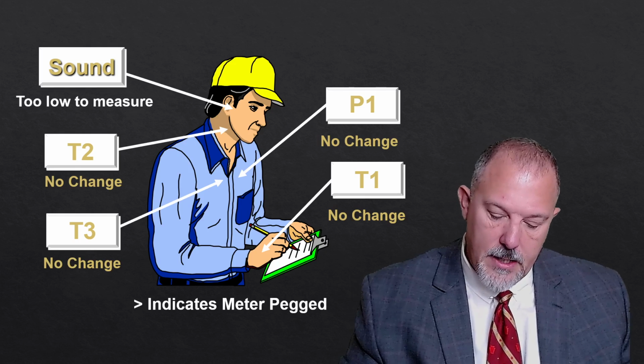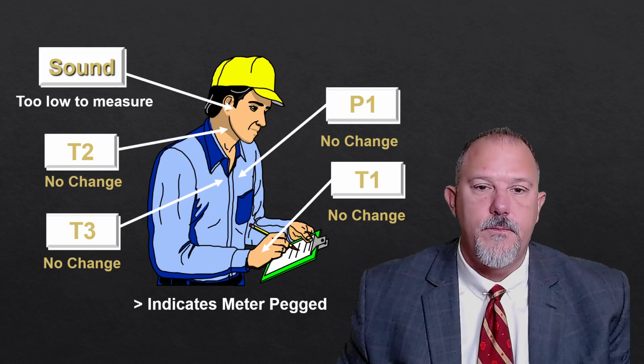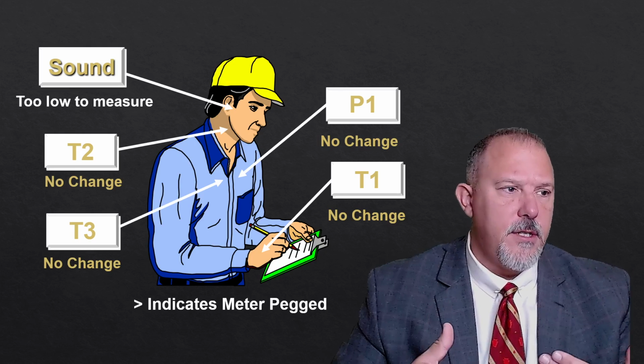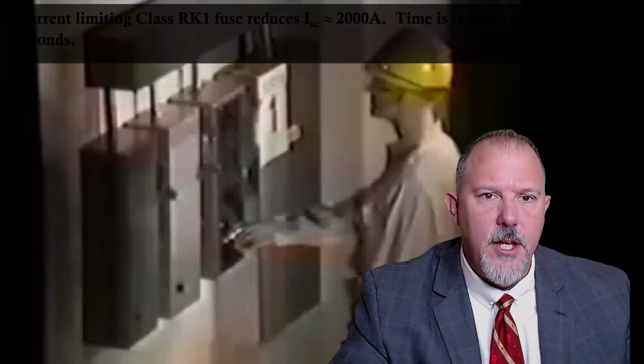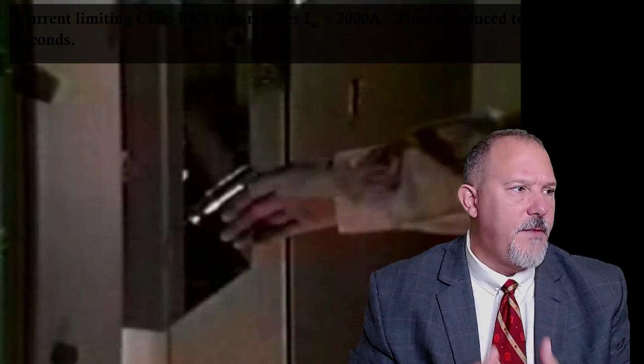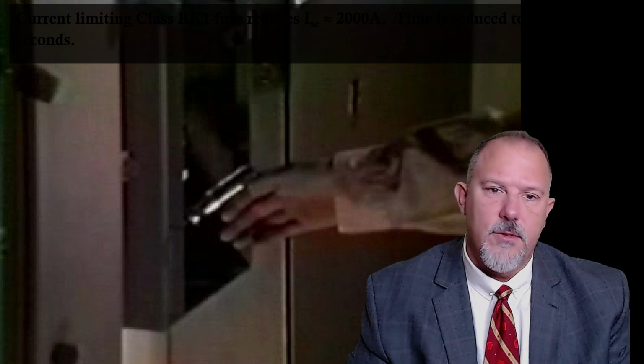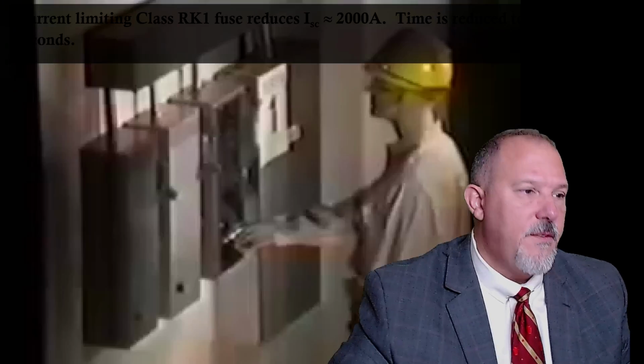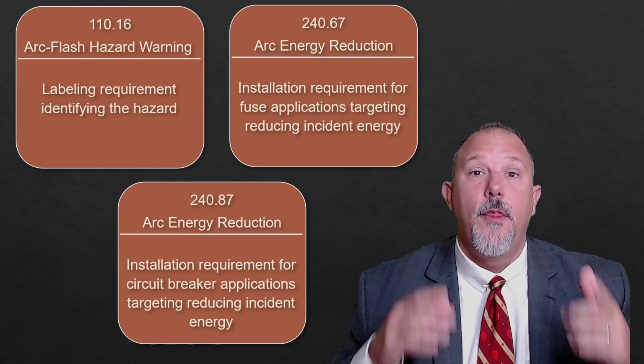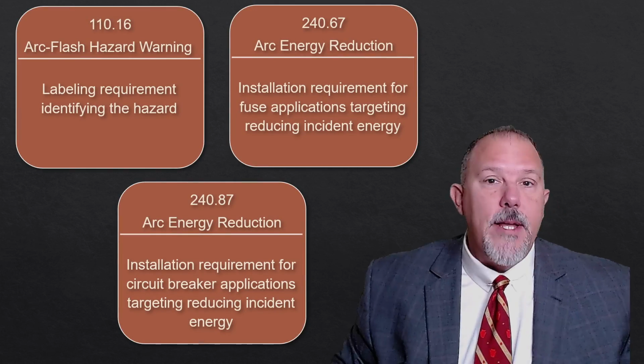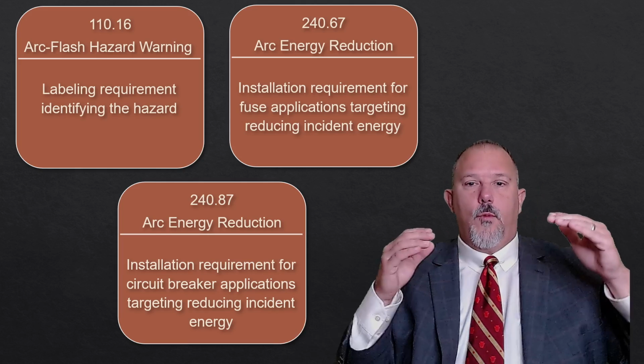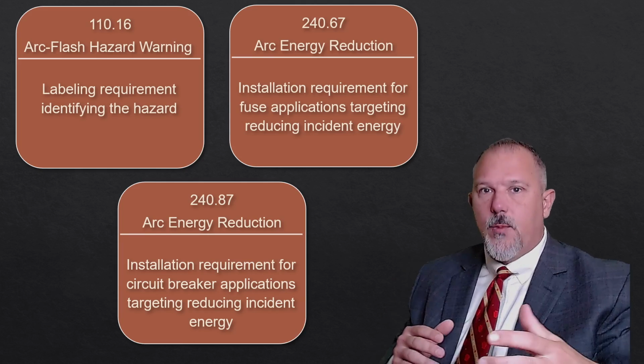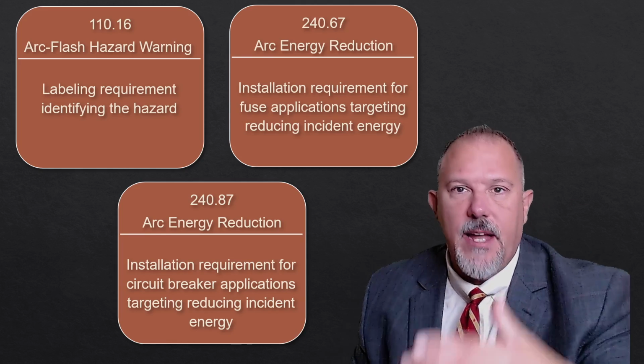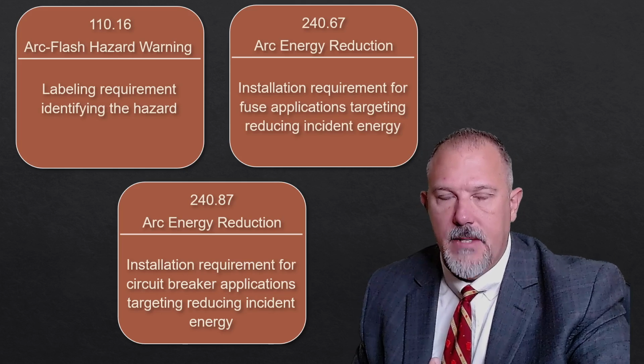So the current limitation, and let's just do that again. Current limitation, a current limiting device limits that fault to such a point that you have reduced the severity of that event. All right, now let's talk about the code. Now we understand what an arc flash event is. We understand to reduce the severity, I need to reduce the clearing time.